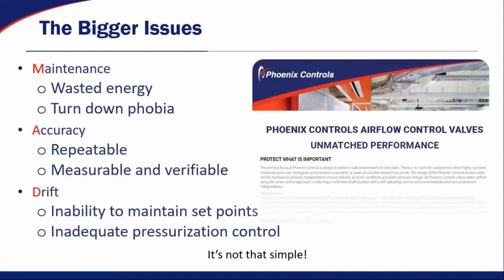So the accuracy we talked about, Phoenix products, plus or minus 5% across the entire flow and pressure range. But when you're talking about airflow control devices that use flow measurement, not only are you not going to get 100% repeatable airflow, but being able to measure and quantify the accuracy is very different than what you have with a third-party certified device like a Phoenix valve. And the last thing is drift, the inability to maintain set points, which will lead to inadequate pressurization control, and eventually you'll have to replace components like pressure transducers and recalibrate things year over year just because of the drifting system.